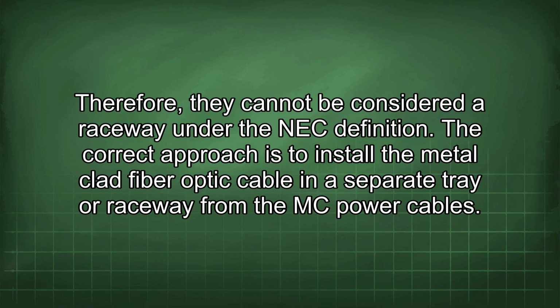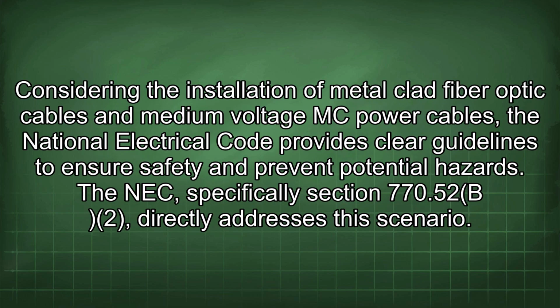The correct approach is to install the metal-clad fiber optic cable in a separate tray or raceway from the MC power cables. Considering the installation of metal-clad fiber optic cables and medium-voltage MC power cables, the National Electrical Code provides clear guidelines to ensure safety and prevent potential hazards. The NEC, specifically Section 770.52(B)(2), directly addresses this scenario.